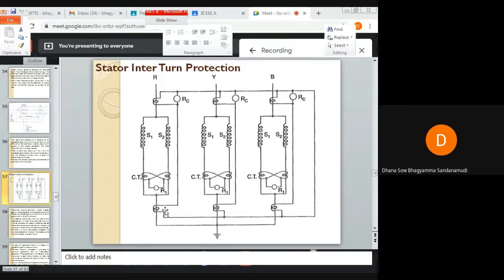But in merz-price protection, the CTs are provided at both ends of the windings, which just measure the entering current into the phase and the leaving current from that phase winding. That's all. So this is a whole R phase winding, and the whole current is measured by these CTs. But if more turns are there within this winding and a fault occurs within those turns, we need some protection.